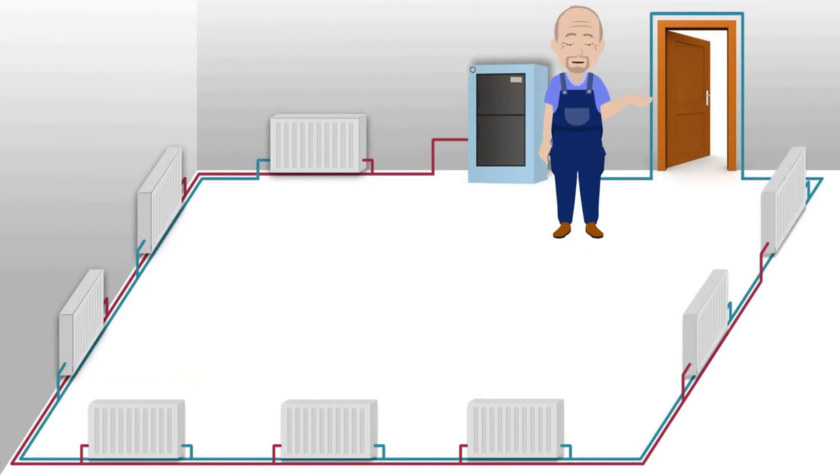The easiest way to bypass them is from the top. Great option. The only downside is that air might accumulate here. An automatic air vent will need to be placed here.